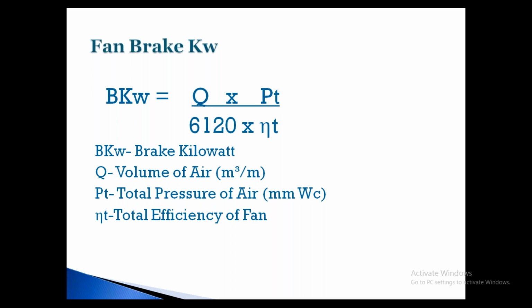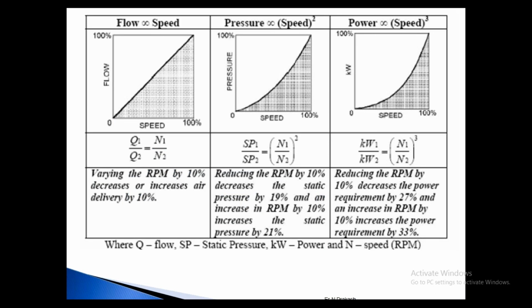So in the existing fans, as you all know, I just want to inform you about how the speed of the fan affects the air volume as well as pressure. So this is the fan law. Speed is directly proportional to the flow. Whatever speed you increase or decrease, equally, if the fan is giving a particular cmh and you reduce the speed by 10%, then volume will reduce by 10%. Simple. If you increase 10%, volume will increase by 10%. Speed is directly proportional to the flow.